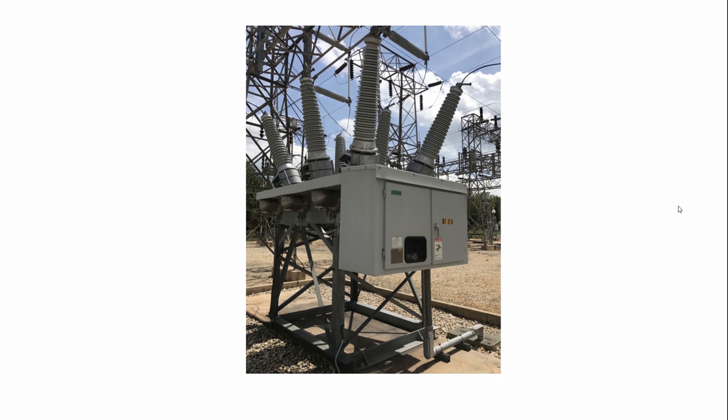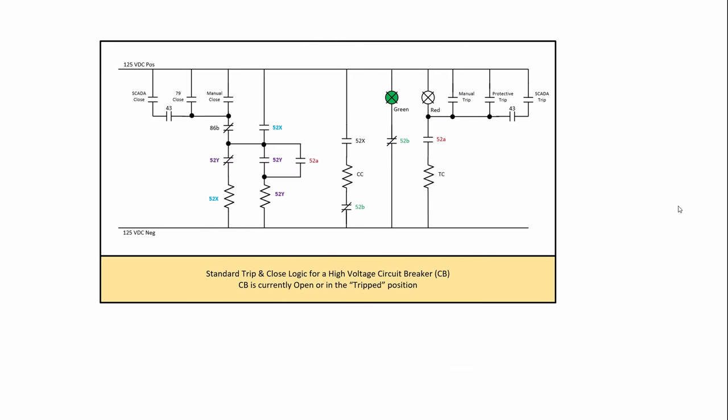There's one on the screen right now that's a 138 kV SF6 circuit breaker and that would definitely have anti-pump logic in it. So let's take a look at the basic logic in a circuit breaker control system. We're looking at this here, right now it's showing in the green or open position.